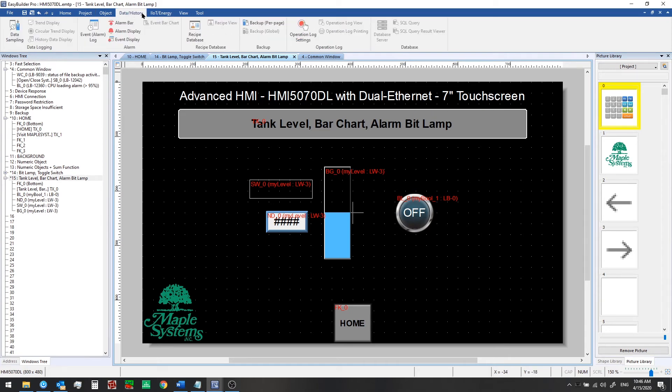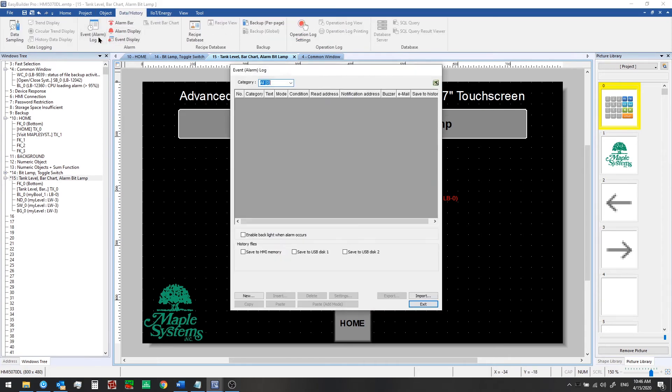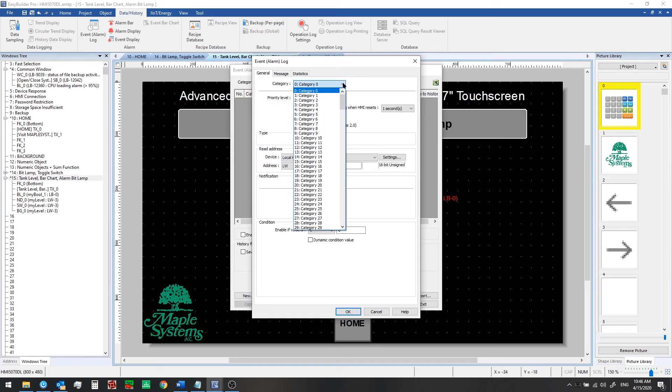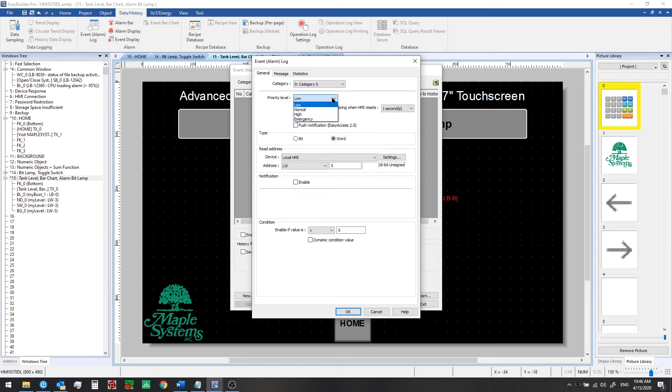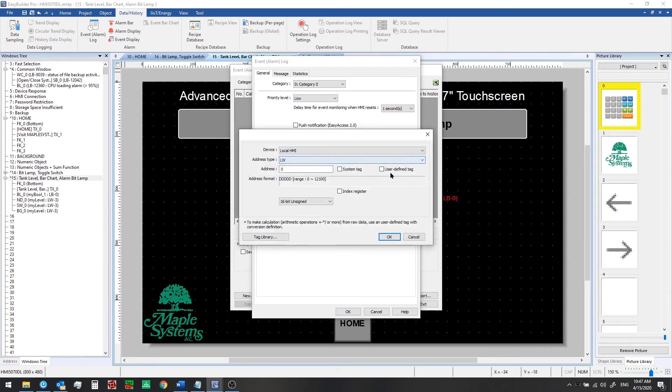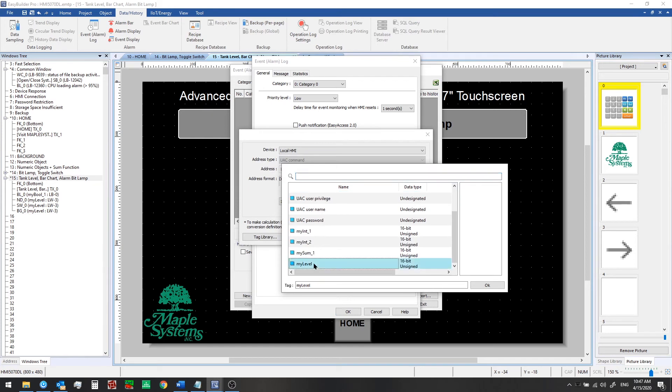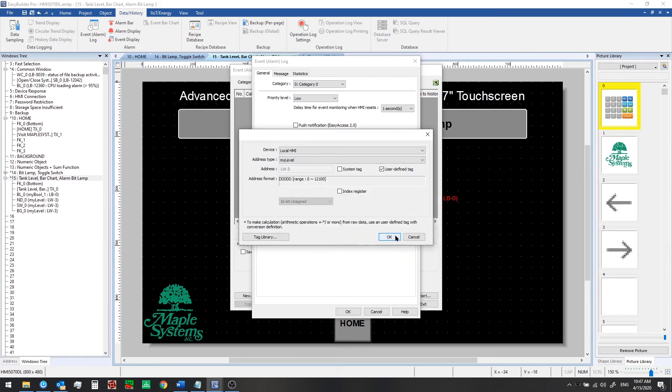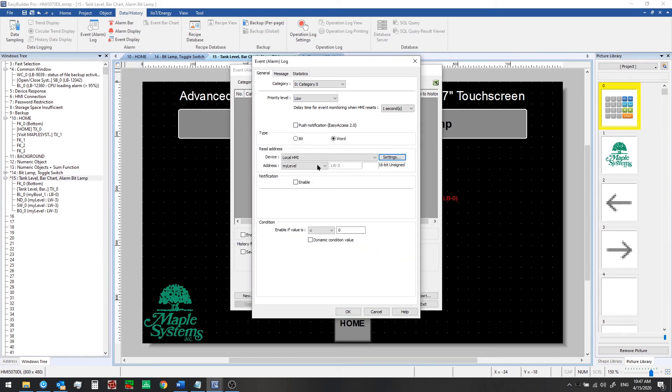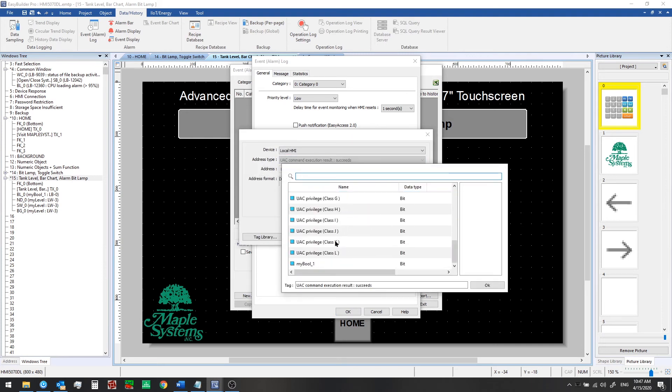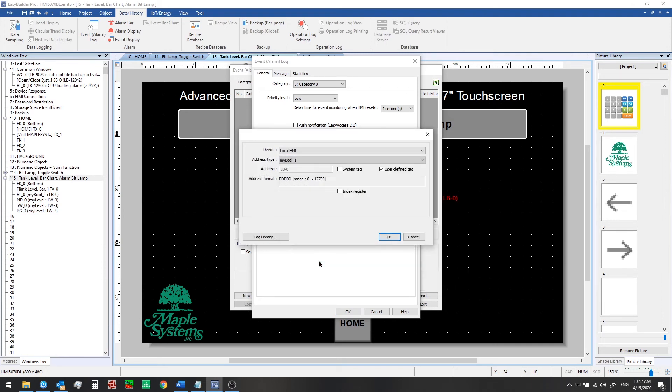So from the data history tab click on event alarm log and we're going to click new category we can leave as zero priority low and we're going to choose our read address now. The read address is going to be the my level tag so we're watching the value there but we want to use the notification feature to turn on a bit. The bit that we want to turn on is the my bool tag that we created earlier.